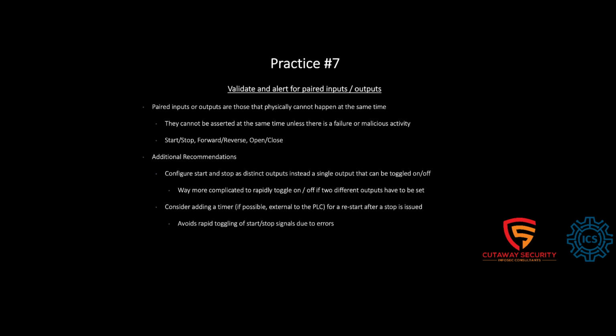Next up is this validate and alert for paired inputs and outputs. This too, again, similar to the previous one, you don't need artificial intelligence. You don't need a lot of extra, non-native functionality, because the PLC can look at all the IO values. And this is one of those things that the PLC can natively do. The paired inputs and outputs are those that are physically unable to happen at the same time. As an example, a motor can be either started or stopped, and the belt conveyor could be going forward or reverse, or a valve could be open or close, or going to open or close, but it cannot be open and close at the same time, right?